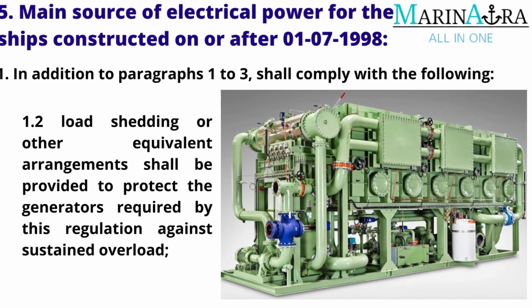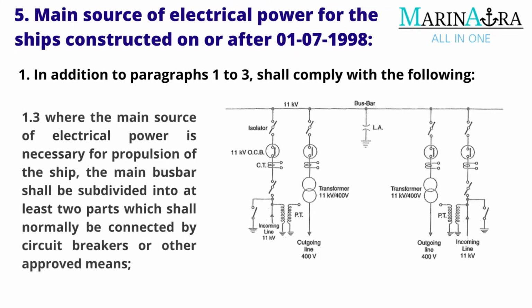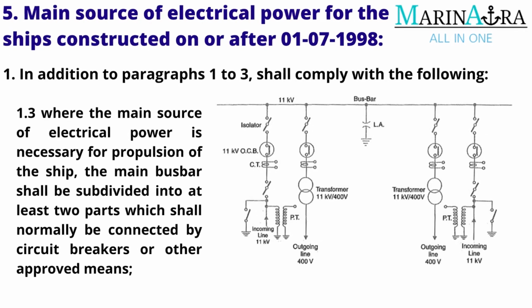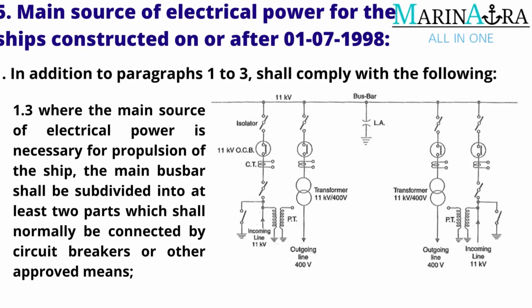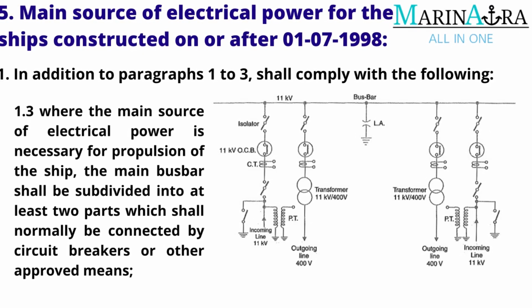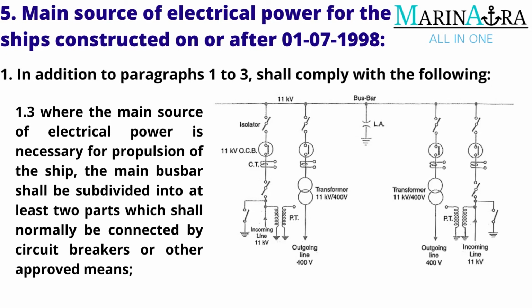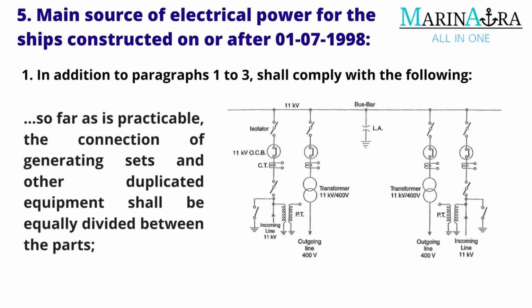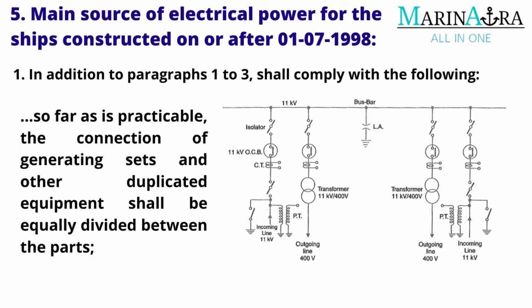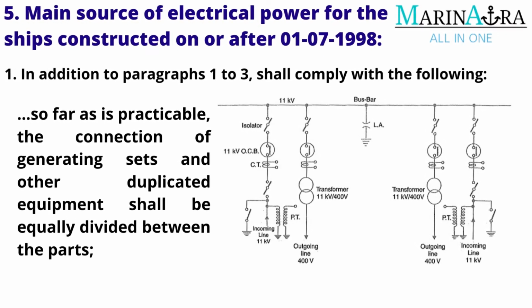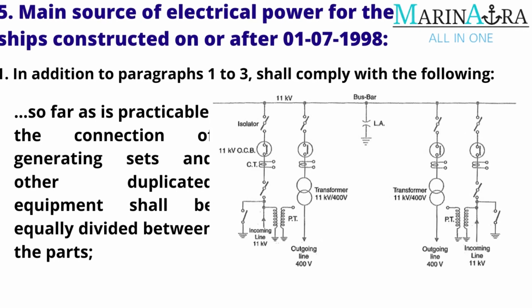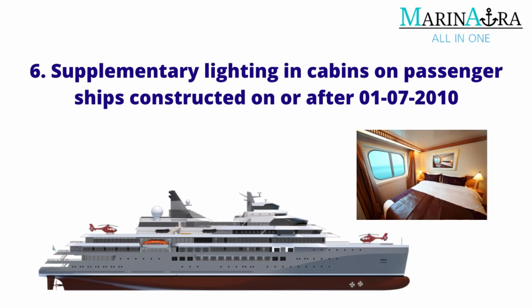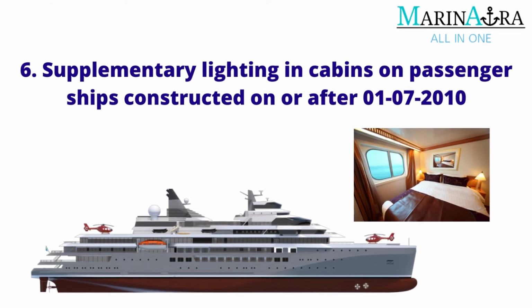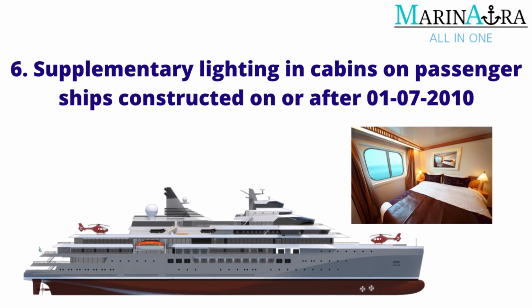against sustained overload. Where the main source of electrical power is necessary for propulsion of the ship, the main busbar shall be subdivided into at least two parts which shall normally be connected by circuit breakers or other approved means. So far as is practicable, the connection of generating sets and other duplicated equipment shall be equally divided between the parts. Sixth, supplementary lighting in cabins on passenger ships constructed on or after 1st of July 2010.